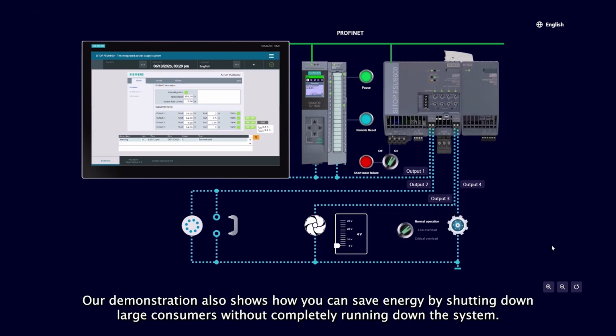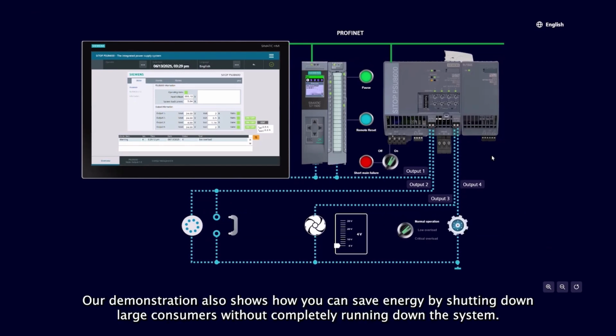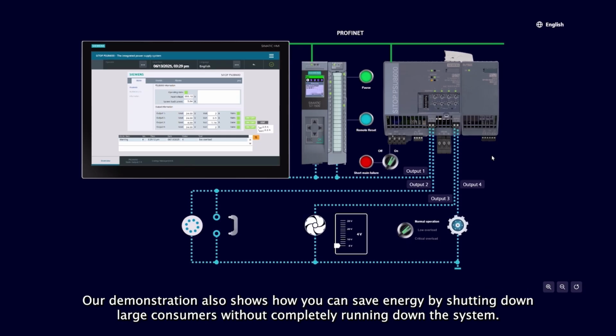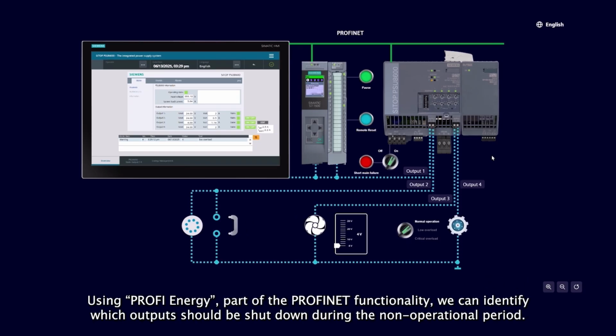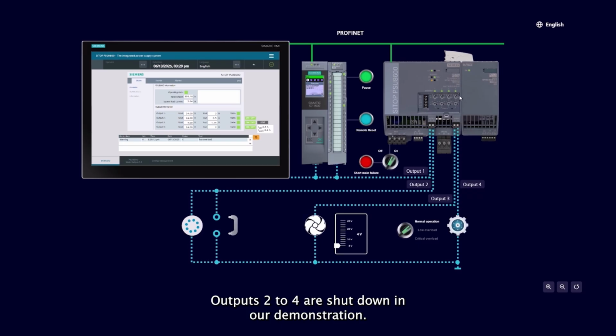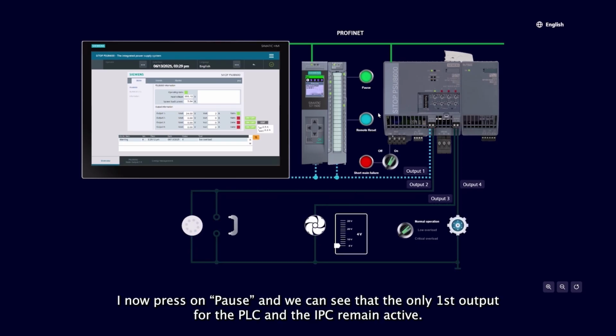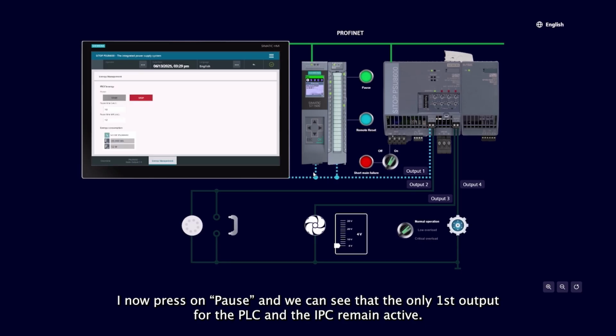Our demonstration also shows how you can save energy by shutting down large consumers without completely running down the system. Using Profi Energy, part of the Profinet functionality, we can identify which outputs should be shut down during the non-operational period. Outputs 2 to 4 are shut down in our demonstration. I now press pause and we can see that only the first output for the PLC and the IPC remain active.